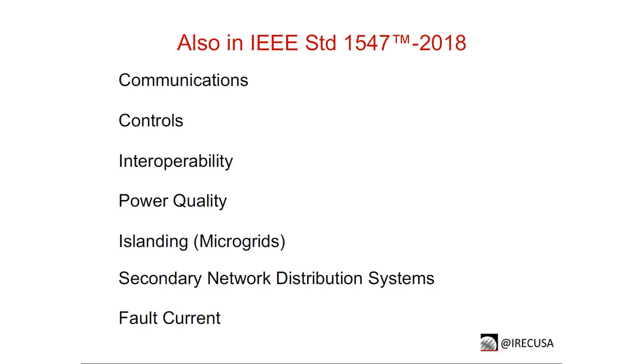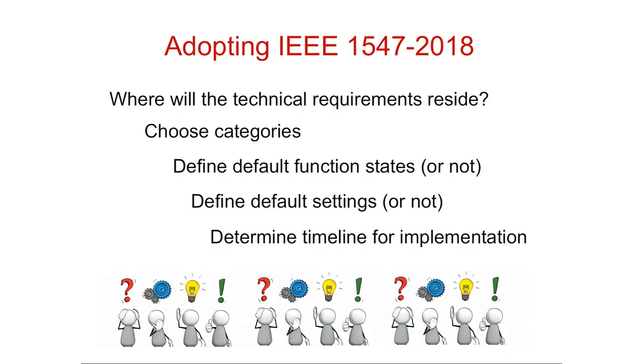And 1547-2018 requires DERs to include provisions for local DER communication interfaces, which could allow more benefits to be realized through monitoring, direct control, and adjusting the settings over time. In the context of interconnection rules and tariffs and guidance documents, these are all going to need to specify which DERs are going to be required to integrate with communication systems and what communication protocols the utilities will need to use to allow for that interface. So expect this to be an evolving and riveting discussion.